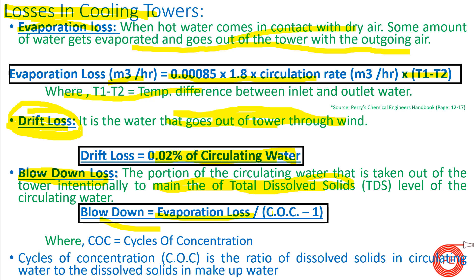Blowdown loss is calculated as evaporation loss divided by (COC minus 1), where COC is cycles of concentration. Generally, cooling tower suppliers offer cycles of concentration around five to seven, meaning a blowdown is required after five or seven cycles. Cycles of concentration is given by the ratio of dissolved solids in circulating water to dissolved solids in makeup water. The total makeup water requirement equals evaporation loss plus drift loss plus blowdown loss.